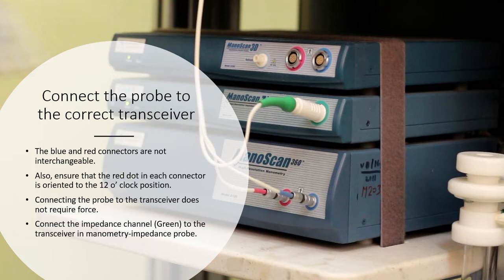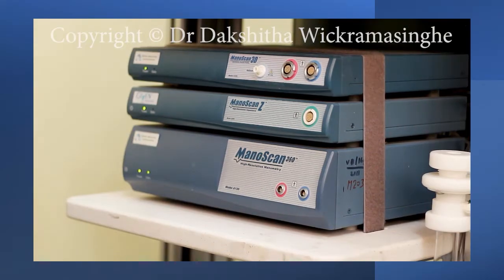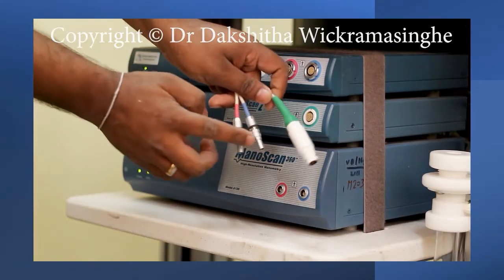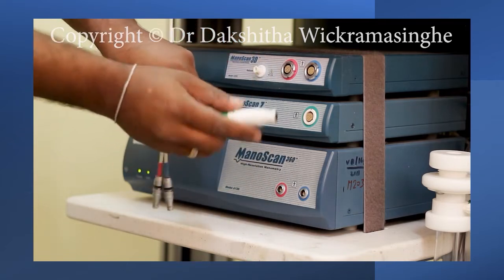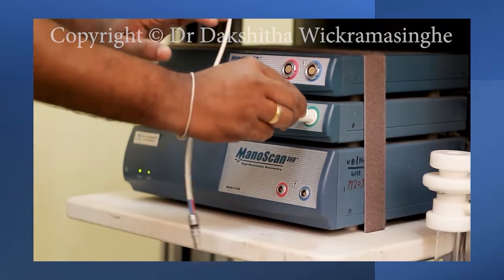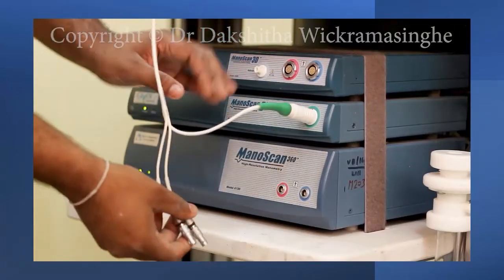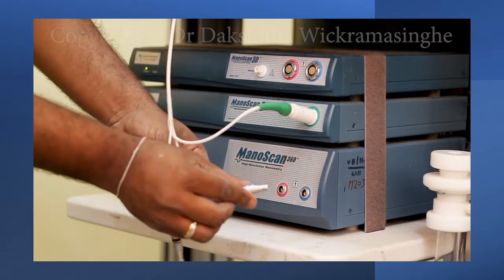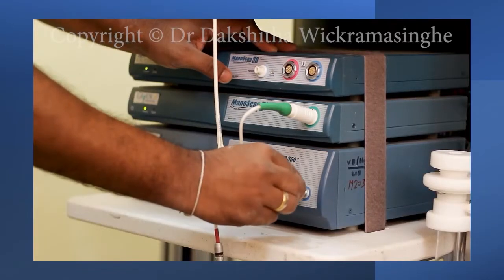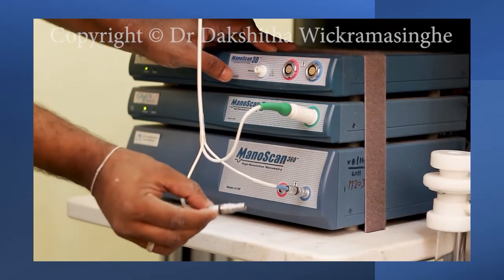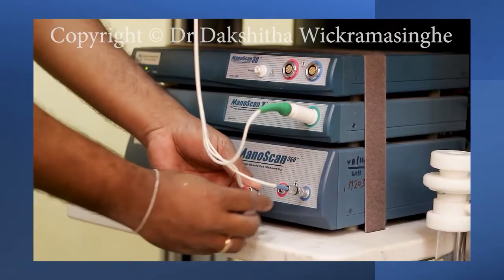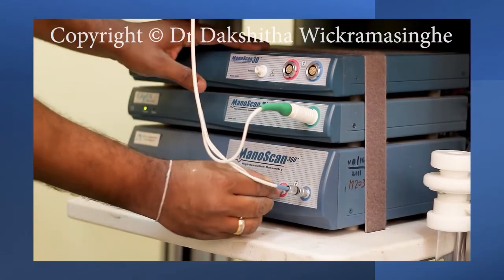Connect the impedance channel, that is the green connector, to the transceiver if using an impedance manometry probe. An impedance and manometry catheter has three connectors. The green connector is for impedance, while red and blue connectors are for pressure measurement. Orientate each connector using the red dot at 12 o'clock position. Follow the color code to connect the appropriate connector. Connecting this does not require force.